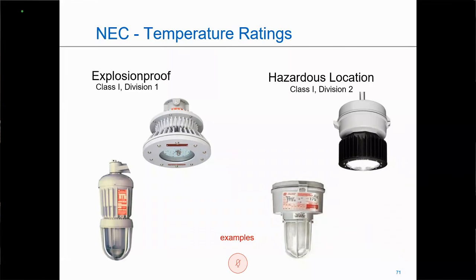And the reason I'm doing this is not a fixture that contains an explosion. It's hazardous location rated. It's designed with construction that'll put up with the abuse, with the rugged nature of a hazardous location area, the corrosive elements. It's designed that if something breaks inside, it can't escape. And it's designed that when gas, if it were to migrate inside, nothing inside the unit is hot enough to ignite those gases.